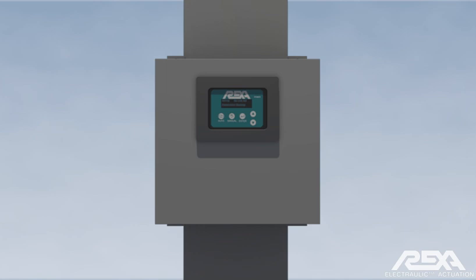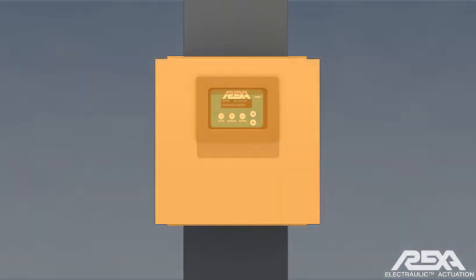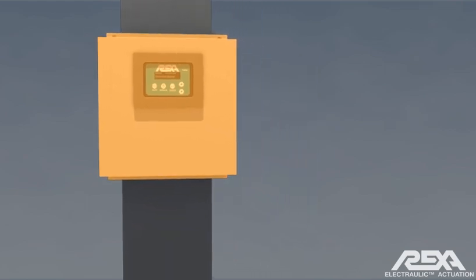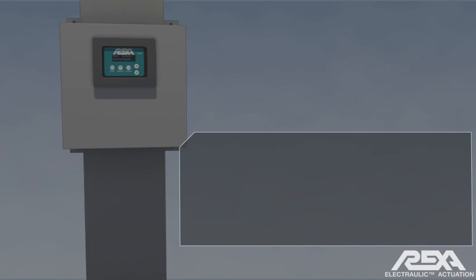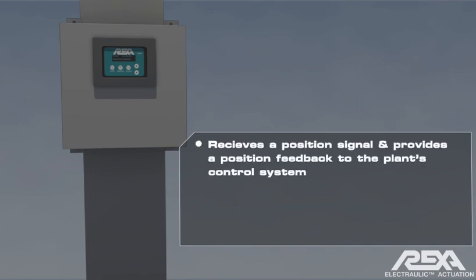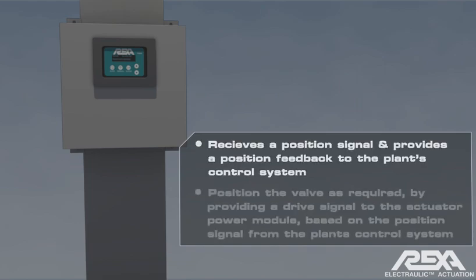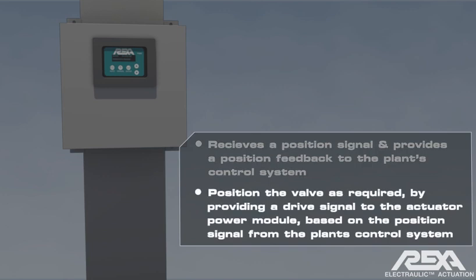The REXA actuator interface with the plant's control system is the local control enclosure. The control enclosure receives a position signal and provides a position feedback to the plant's control system. Its other function is to position the valve as required by providing a drive signal to the actuator power module based on the position signal from the plant's control system compared to position feedback from the actuator's cylinder.